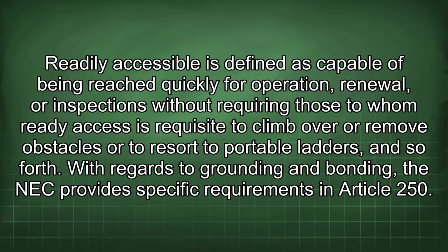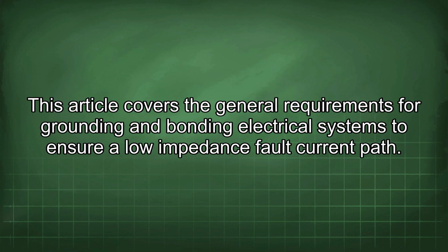Readily accessible is defined as capable of being reached quickly for operation, renewal, or inspections without requiring those to whom ready access is requisite to climb over or remove obstacles or to resort to portable ladders, and so forth. With regards to grounding and bonding, the NEC provides specific requirements in Article 250. This article covers the general requirements for grounding and bonding electrical systems to ensure a low impedance fault current path.